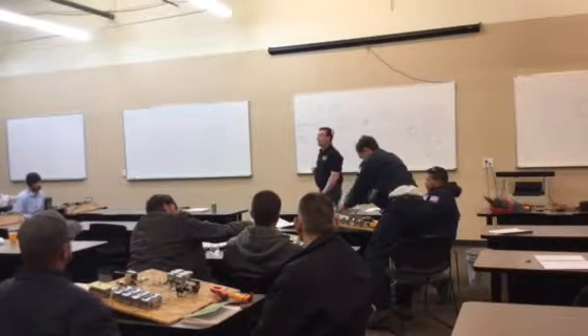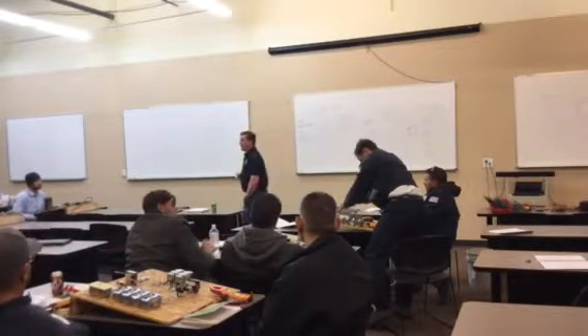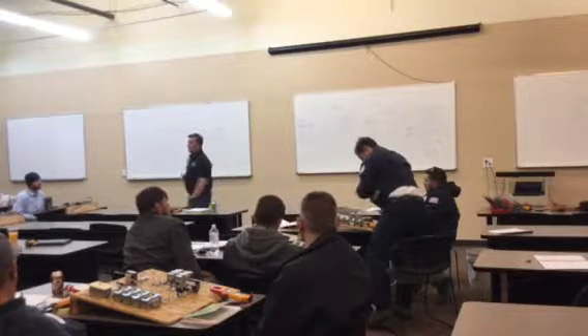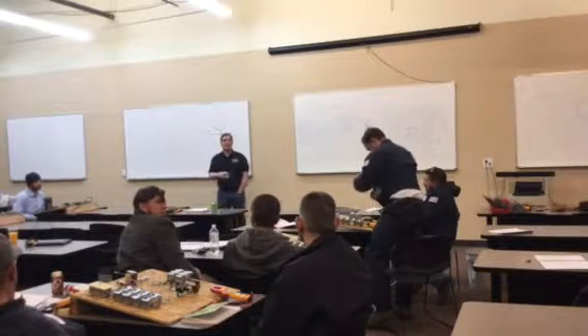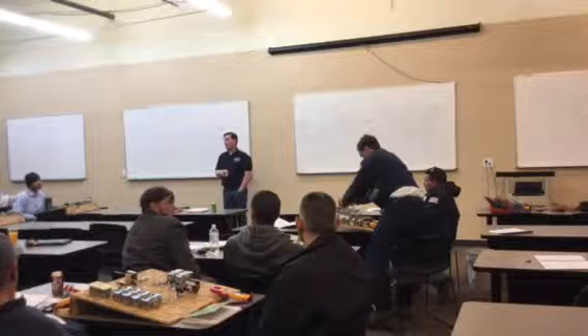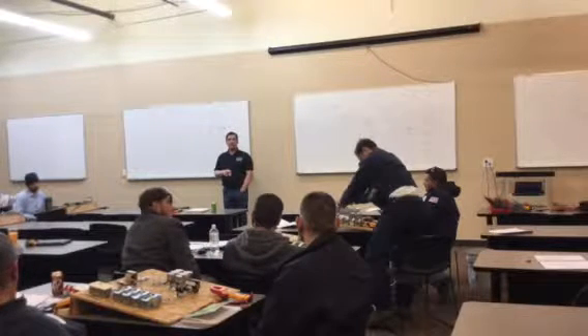This is nominal 24 volts. Notice it's a little on the high side, and that's pretty normal. Most of our 24 volt transformers typically put out 28 to 30 volts AC, and that's what we expect to see.